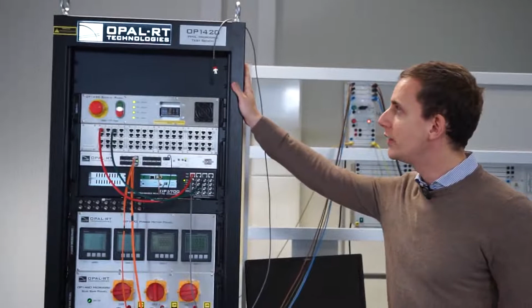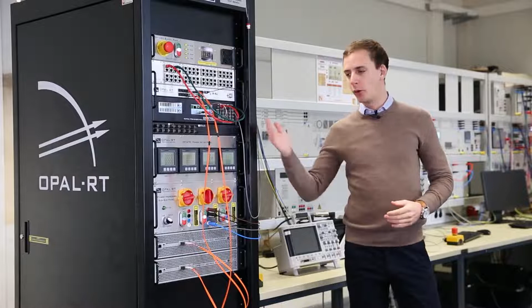I think now it's time to have a deeper look at each component of this test bench by looking at the OP1420 PHIL microgrid test bench in the University Duisburg-Essen laboratory. This safety box provides low voltage supply to other components and controls the three-phase input power on the front side. It also allows to disconnect DC sources and high power components of the test bench in case of fault.